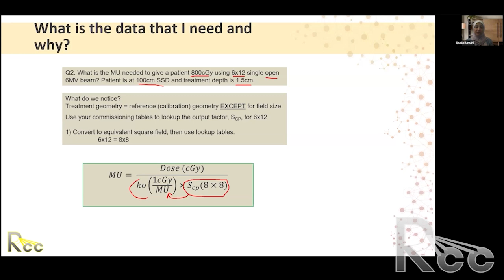K0, this number, is only true for a 10 by 10 field size, 100 cm SSD, and a depth of Dmax in our example, right? So anything that is not 10 by 10, open, Dmax, 100 cm SSD, we have to take it back to that. So we have to do all these corrections.